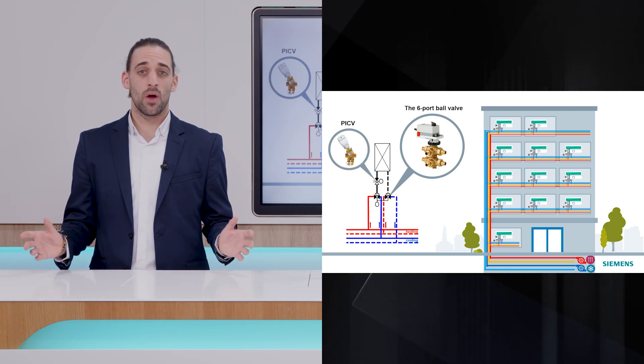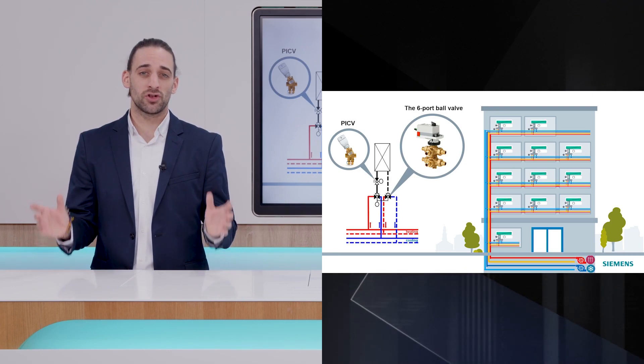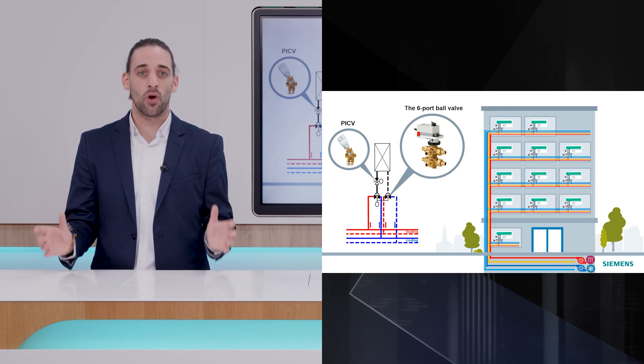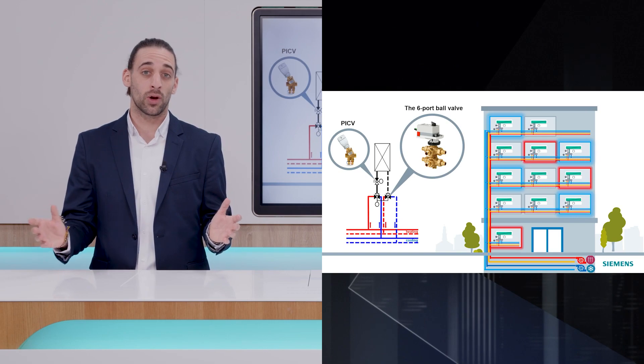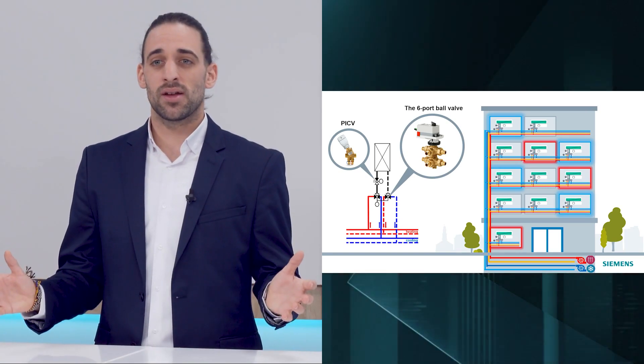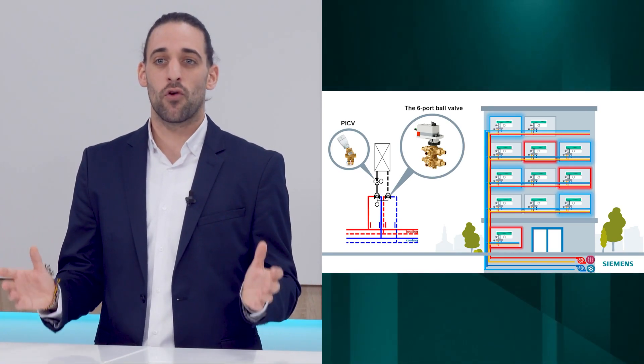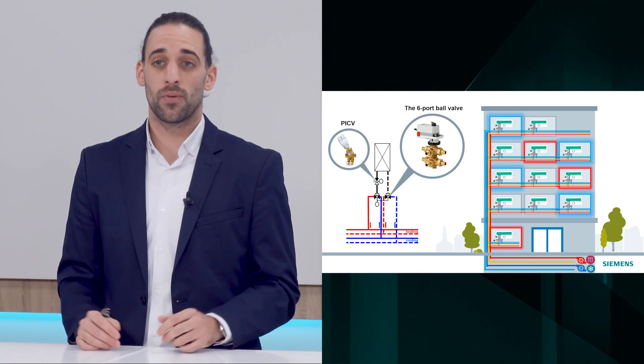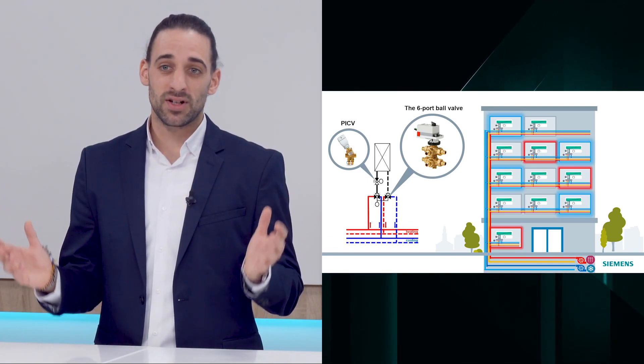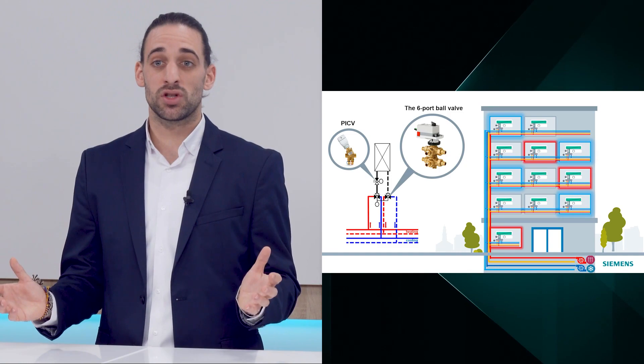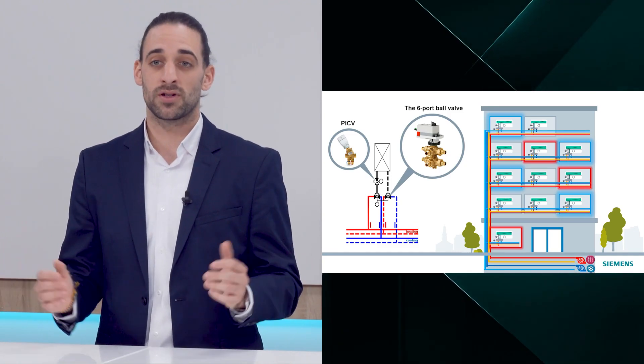However, one problem still remains. You still have to meet the different maximum flow demands for heating and cooling. PICVs can only be manually preset for a single maximum flow value. Therefore, dynamic presetting is needed when the system switches from heating to cooling or vice versa.